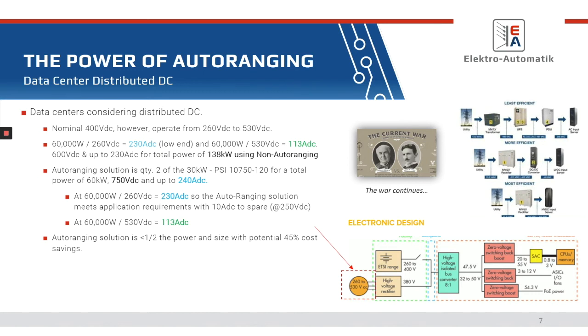So with a standard, traditional, square operating power supply, you have to calculate both the 230 amps DC and the 600 volts DC. Multiply that together, you get your 138 kilowatts. So again, this is another example where, just because you have these high voltage, low current and low voltage, high current conditions, the result is that the non-auto ranging power supply would have to be more than twice the power level of the actual server.